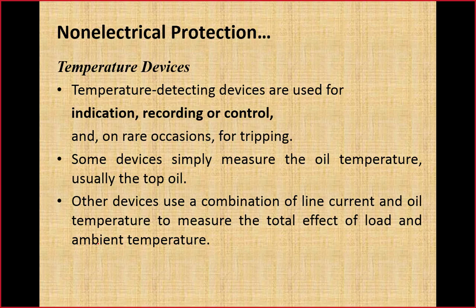But if the current is higher than the rating, or you can say much higher than the rating, and temperature is high, that is a clear indication of overloading of the transformer. So that's why temperature plus the current reading will give us a better picture of the problem as compared to just monitoring the temperature.